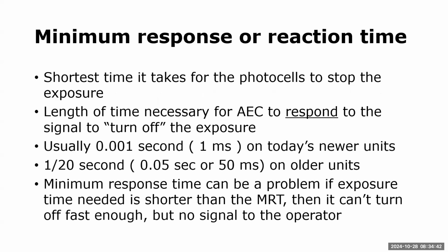So minimum response or reaction time. See that it is called two different things. Minimum response time or minimum reaction time. So that is talking about the shortest time that it takes for the photocells to stop the exposure. Meaning it's the length of time necessary for the AEC to respond to the signal to turn off. So it is the shortest response time that your machine has.